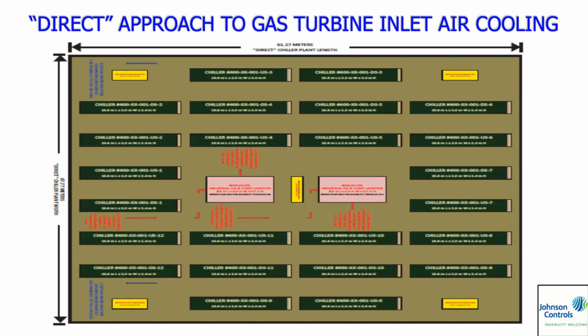Okay. So in this case, we had a medium voltage coming to the site. And so the analysis was air-cooled chillers, all 400 volts. And then all these little yellow boxes you see are step-down transformers. We were taking 3,300 volts down to 400 volts. So we got the step-down transformers, strategically located. And then what you see here in the pink are pumping skids, where we had pumps that was pumping the chilled water through the system. I'm not showing the piping interconnections. That's another drawing. But so essentially, we have to space these so that the two heat exchangers aren't fighting for the same heat rejection area.